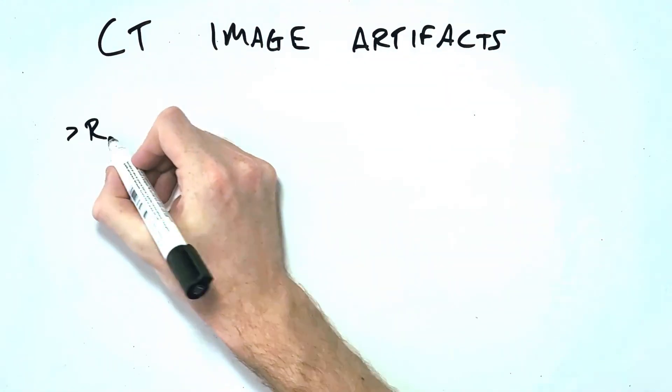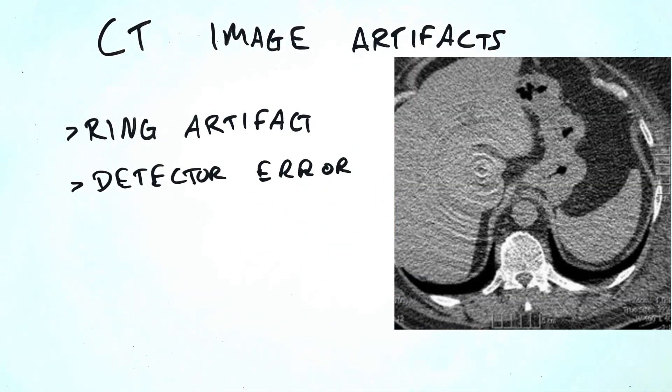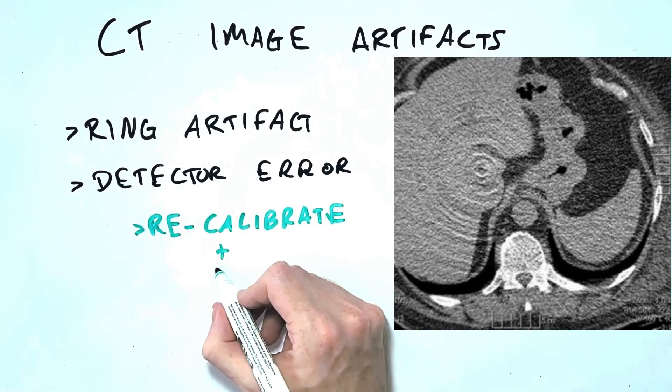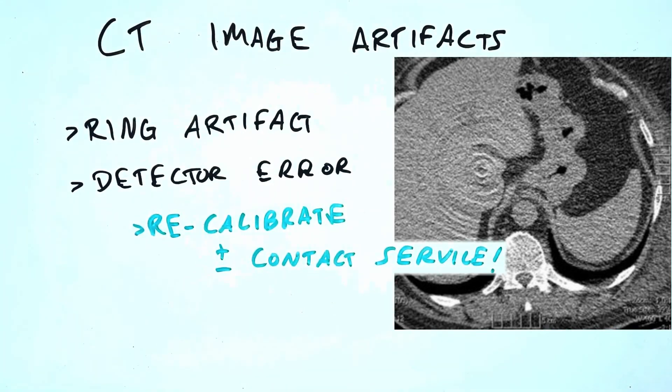Finally you may see a ring artefact which looks like ripples on a pond. This is caused by a detector issue and can sometimes be fixed by redoing your calibrations. However, sometimes this type of artefact will require the attention of a service engineer.